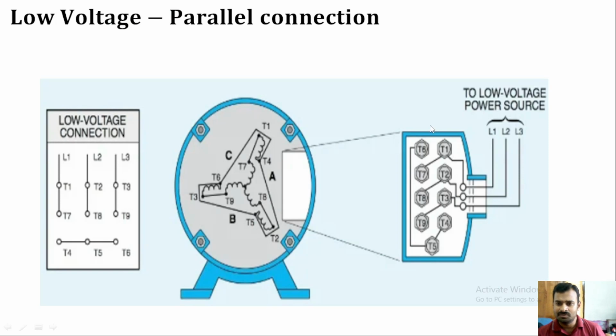Now here you can see in the motor nameplate, you will have the terminal box like this. L1 is connected to T1 and T7. L2 is connected to T2 and T8. And L3 is connected to T3 and T9. So this is how the connection will be made. And T4, T5, T6 will be shorted.